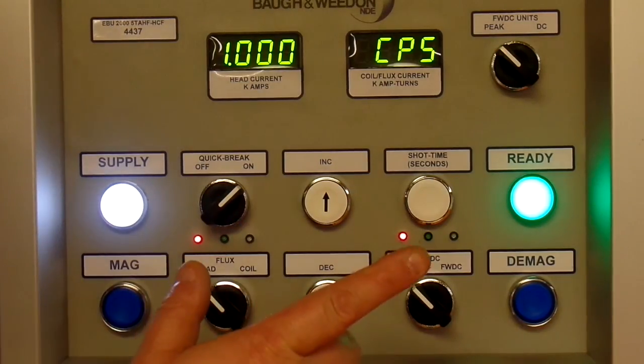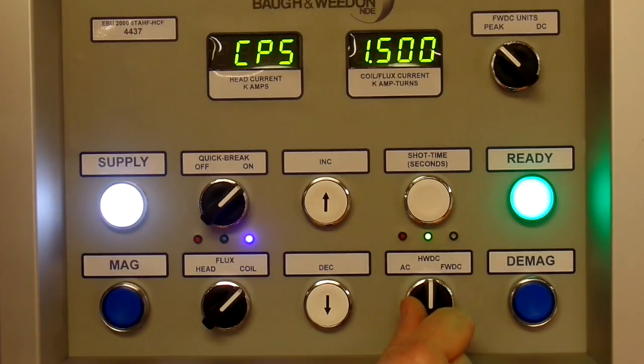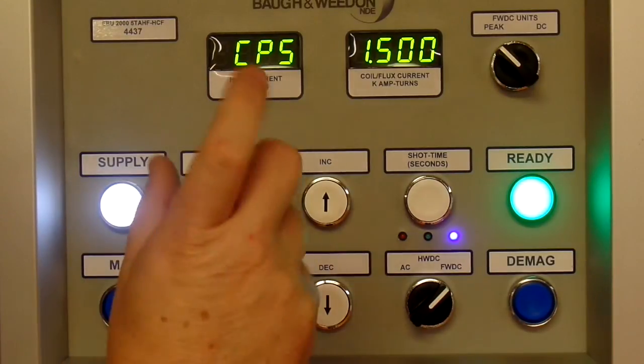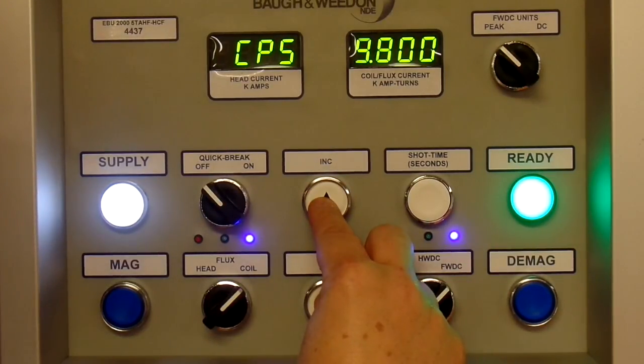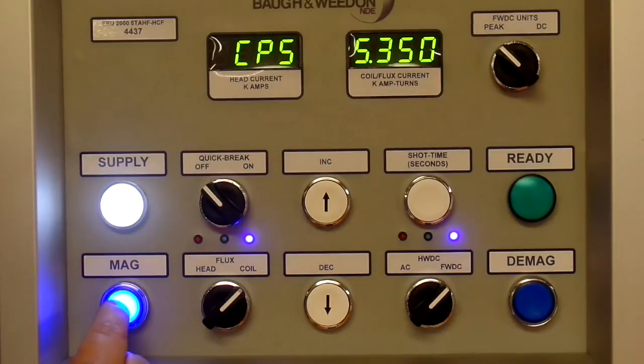On this bench we have three phase full wave DC. We have coil and flux, therefore we have to supply quick break. I'll switch this in — we'll switch to coil and full wave. I'll keep quick break off for now and you'll see the difference between on and off. We'll select a current in the coil at 6000 amp turns and perform a mag. That's with quick break off and with it on.